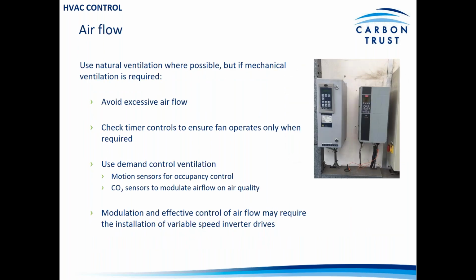And indeed, as I mentioned just there, airflow is important as well. In larger buildings, you'll often see centralized air handling units, which can provide heating and cooling to a space through the ventilation system. So it'll often be supplying air and extracting air to the space, and avoiding excessive airflow in those circumstances can minimize your heating and your cooling loads. So timer control again will be important there, but in addition to that, the use of CO2 sensors in particular can help modulate the airflow based on the air quality.